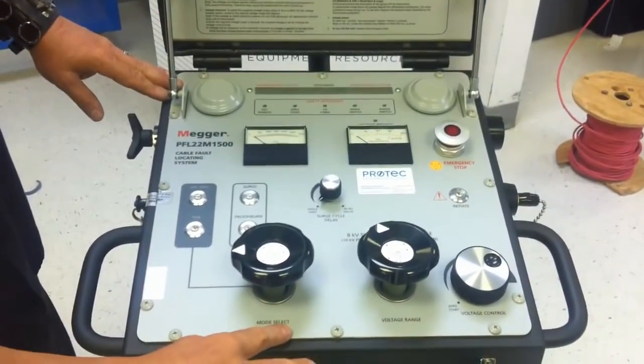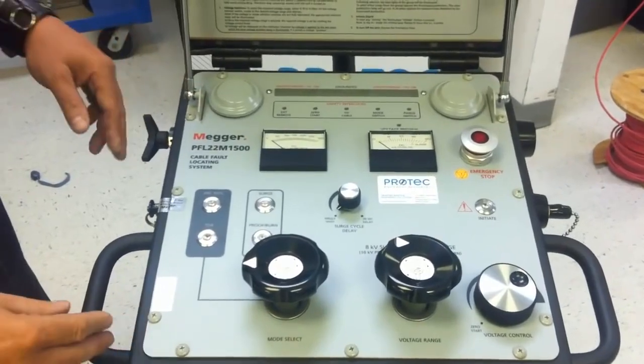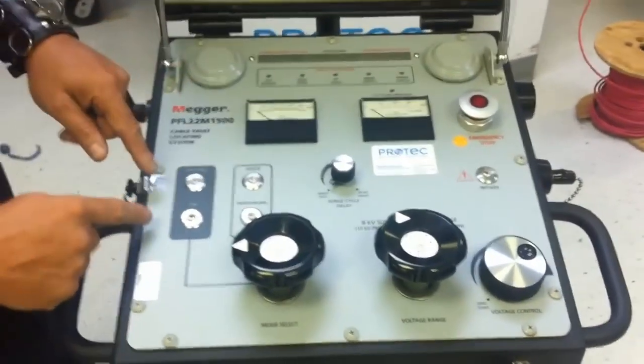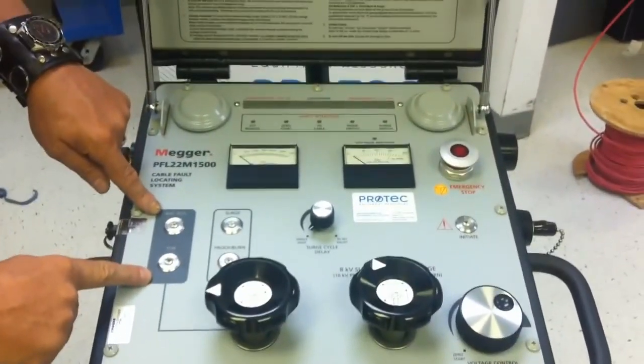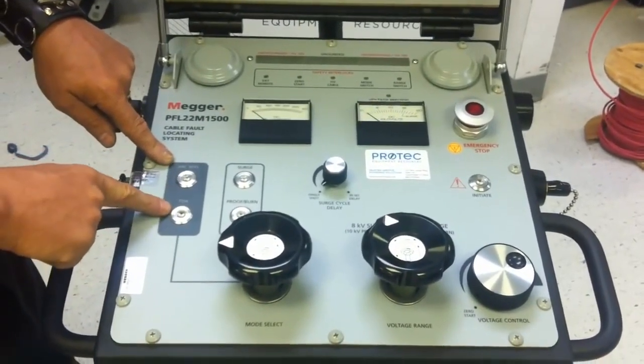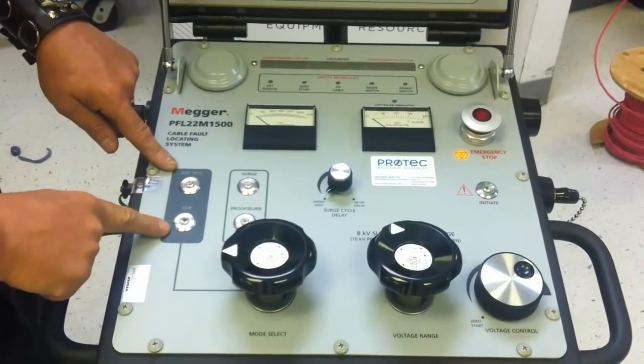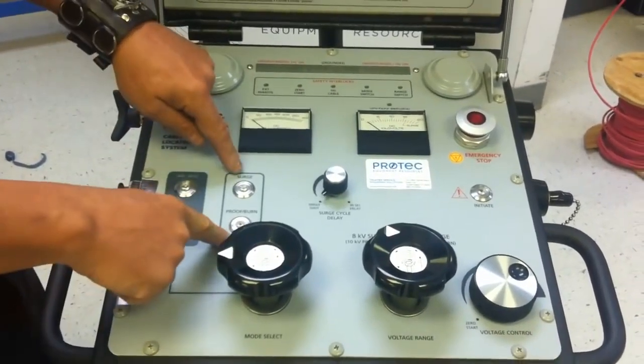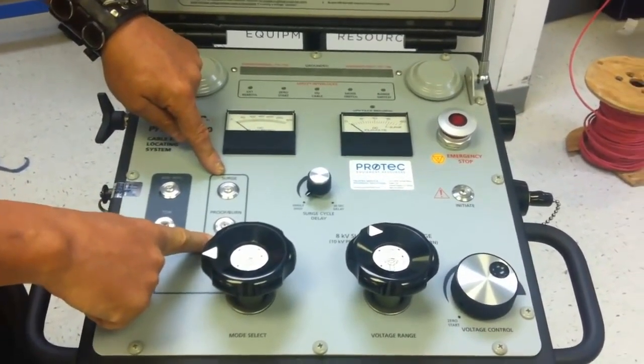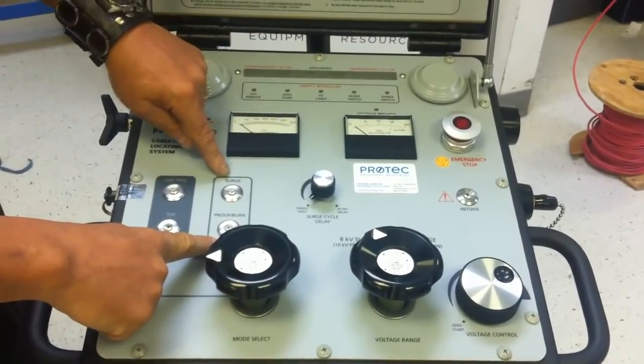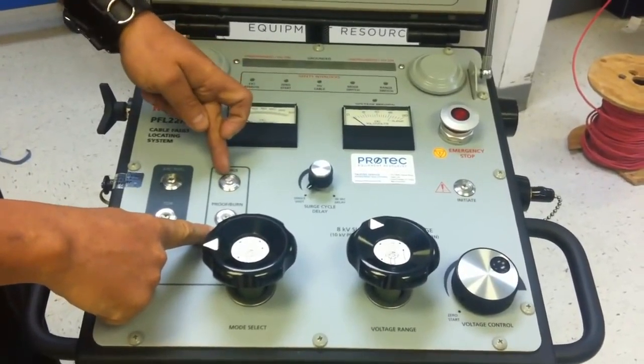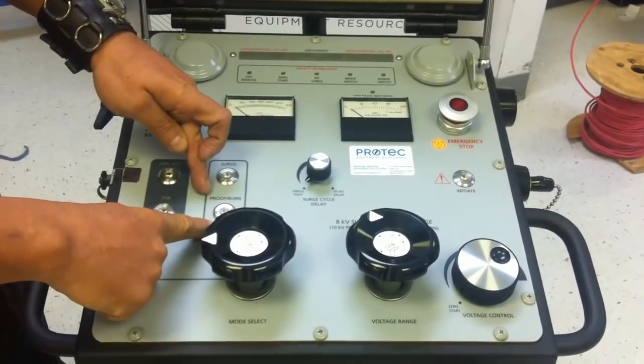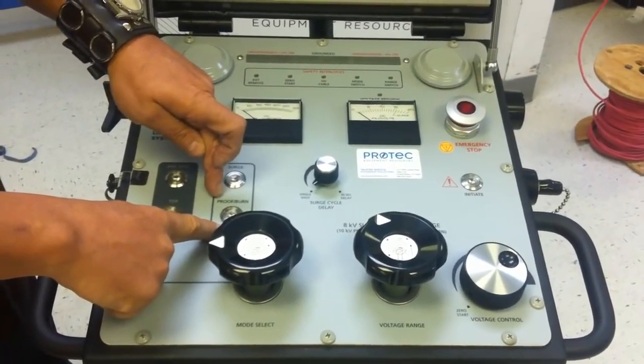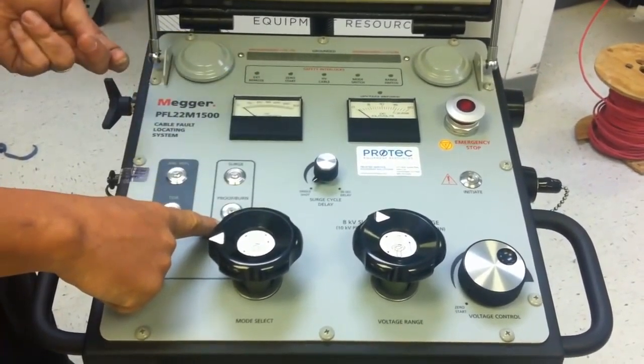You have the mode select section over here, which will in essence allow you to do either coupling to your radar devices, arc reflection, time domain reflectometry, or pulse echo mode, or to do your thumping or high voltage direct mode, where surge would be direct thumping, and to activate your internal DC proof tester or burn down circuit.